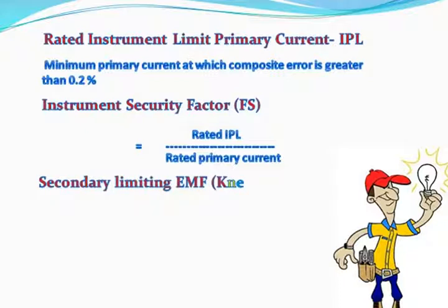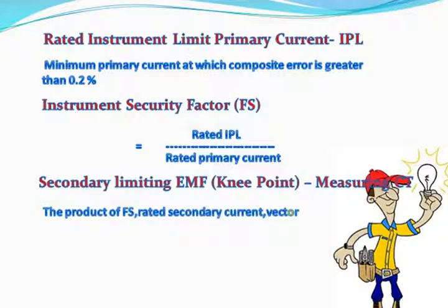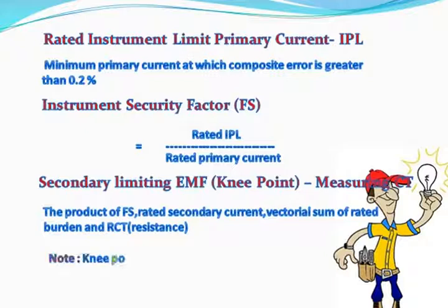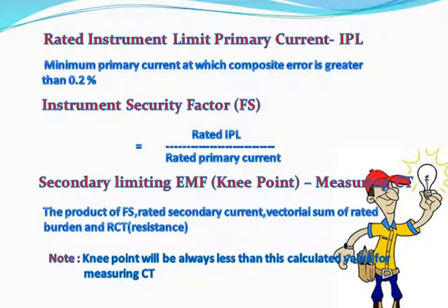The knee point, that is the secondary limiting EMF for measuring CT, is the product of FS, rated secondary current, and the vectorial sum of rated burden and RCT. Please note that the knee point will always be less than this calculated value for measuring CT.